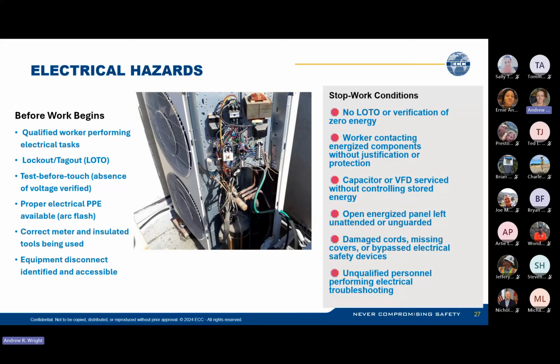Worker contacting energized components without permission or justification. Capacitor or VFD serviced without controlling stored energy. VFD means a variable frequency drive. It's a motor controller that changes the speed of the motor, essentially. Open energized panel left unattended. So if you pull the face off a panel, or like in the picture in the middle, if you just leave that open and it's hot, don't do that. Damaged cords, missing covers, bypass electrical safety devices, unqualified personnel performing troubleshooting, that sort of stuff.